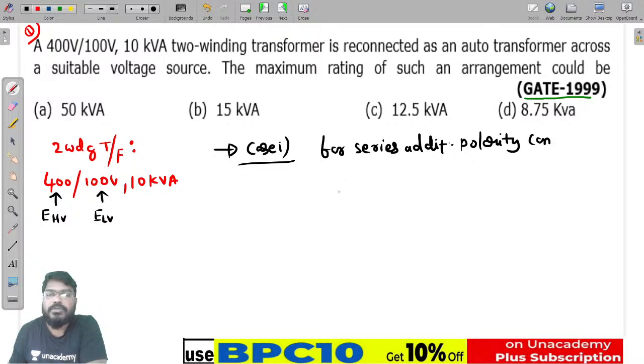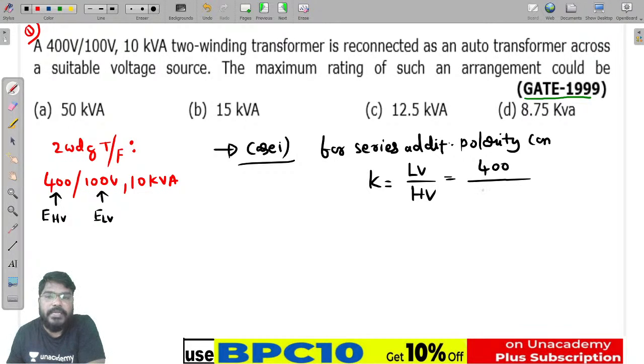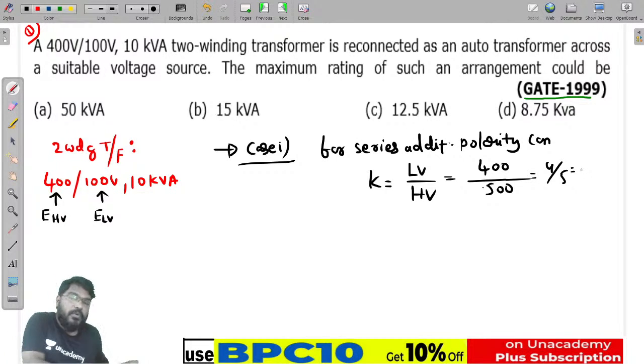For the polarity connection, K is equal to low voltage divided by high voltage. This is the suitable voltage source. Here low voltage is 400, and high voltage is EHV plus ELV, since this is a series polarity connection. So now it is 400 and 500, giving 4 by 5, which equals 0.8.